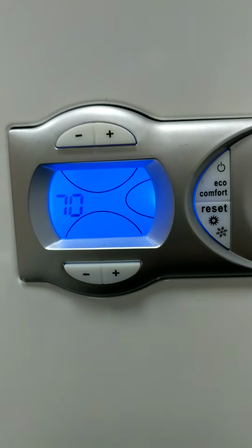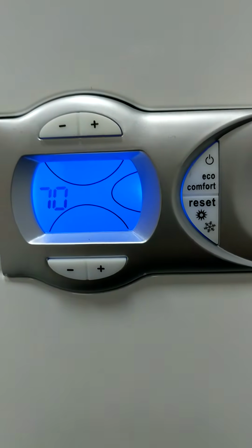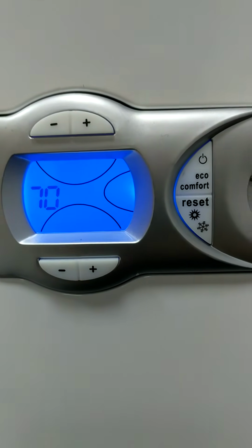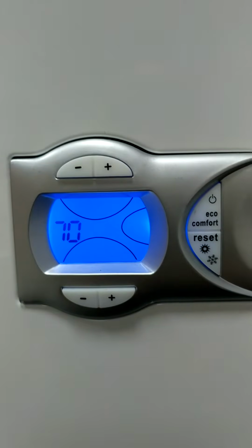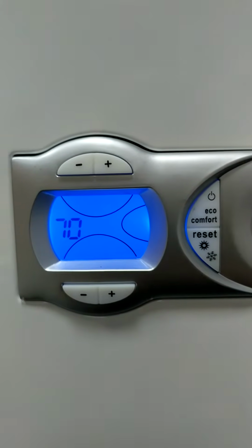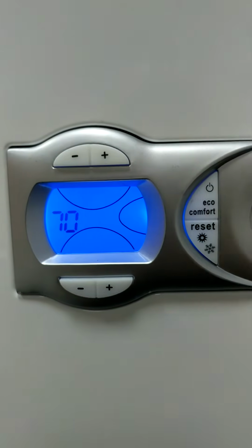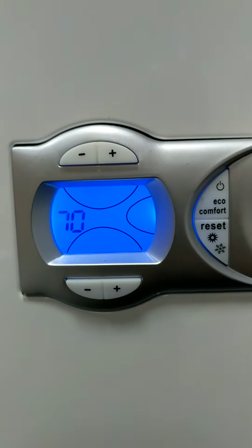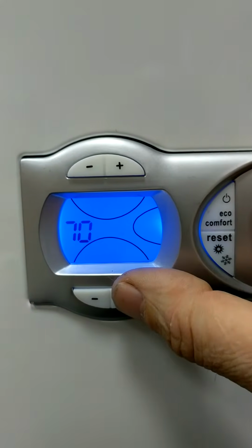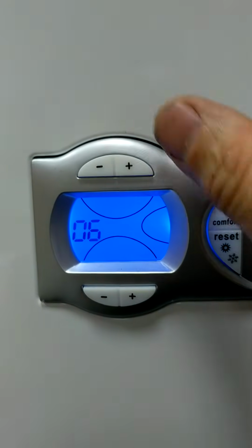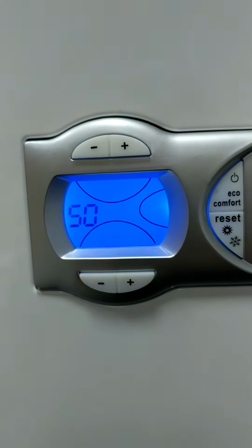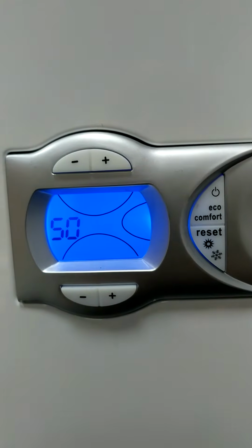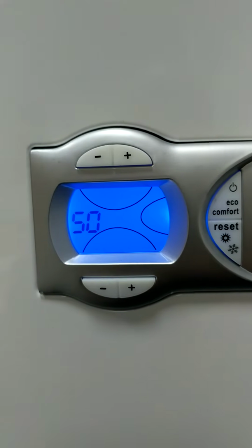So if you want to set it at 60 degrees, you have to set it at 50. If you want to set it at 70, set it to 60, but it will get to the temperature that you really did desire, which is an extra 10 degrees. So, and then we're going to go to parameter 6. This is the output, how much load the boiler's got to do.